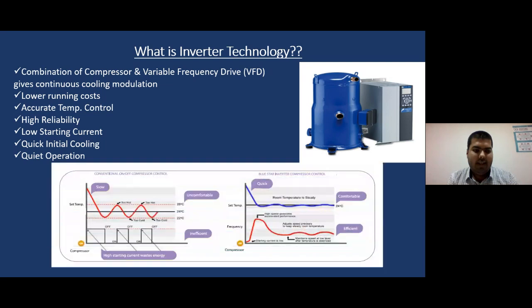As you can see in this graph, the left side is the conventional on-off compressor cycle, like my fixed speed machine, and the right side is the inverter compressor control. If you see the compressor working in the fixed speed machine, there are various on-off cycles. My compressor would go on, then go off, then go on again, and it leads to inefficiency of the machine. When my compressor goes on, the temperature goes down, then the compressor goes off, and the temperature goes up again. You would not feel very comfortable in the room.